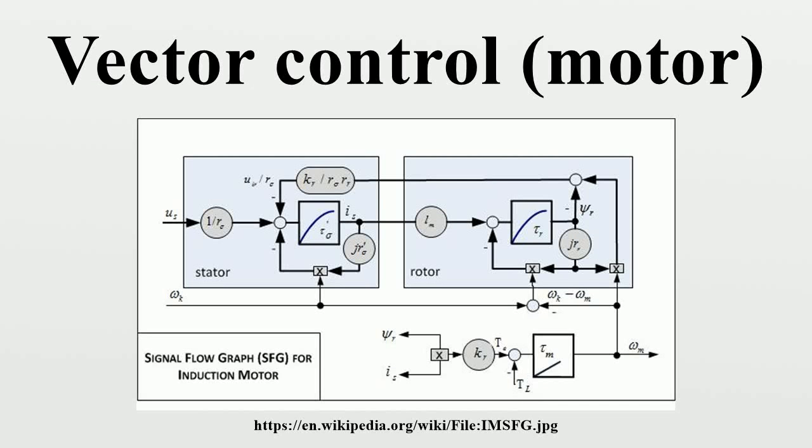Vector control, also called field-oriented control, is a variable frequency drive control method where the stator currents of a three-phase AC electric motor are identified as two orthogonal components that can be visualized with a vector. One component defines the magnetic flux of the motor, the other the torque.